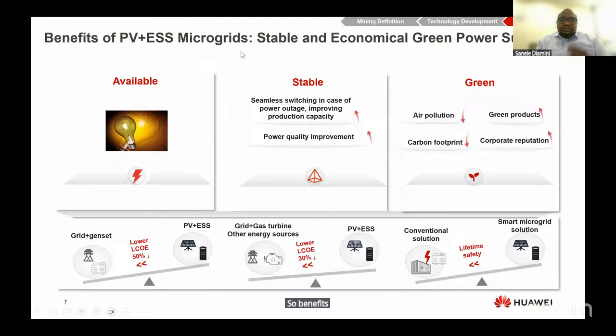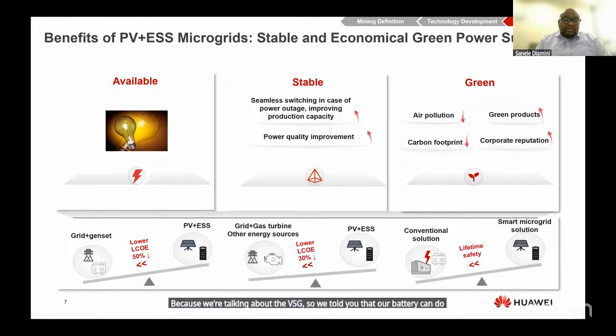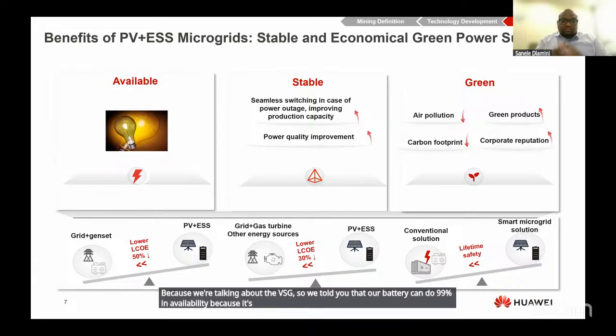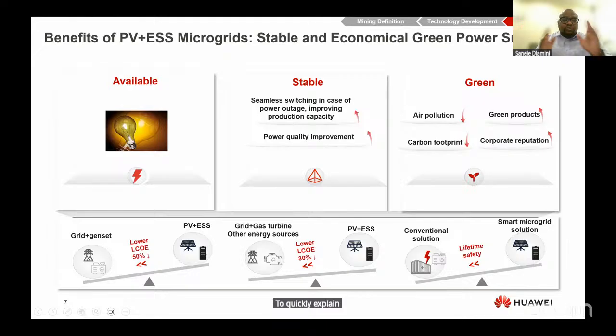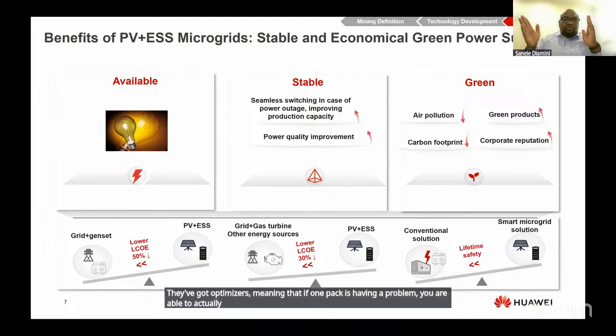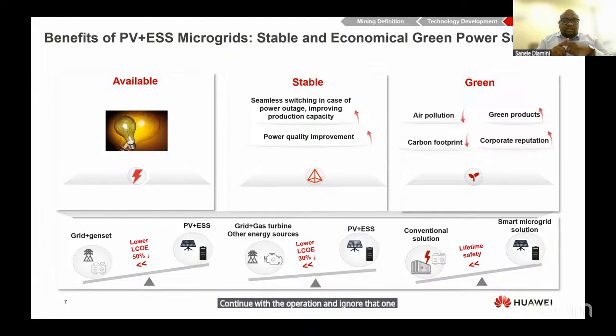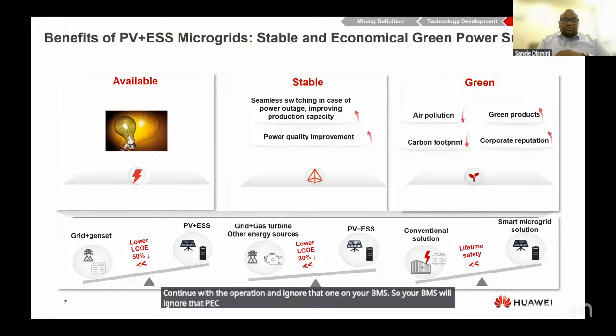So benefits of the PV and ESS and microgrid. So we're looking at the availability on that, because we're talking about a VSG. So we told you that our battery can do 99% availability, because it's actually modular. There's a lot on the battery. We can dive in one day on that. Today we have a short time to explain our battery, but our battery, to quickly explain it, is fairly modular. Even our packs, they've got optimizers, meaning that if one pack is having a problem, you are able to actually continue with the operation and ignore that one on your BMS. So your BMS will ignore that pack and continue with operation. And also, if the SOCs are not balanced, our BMS will actually balance the SOC on the system itself.